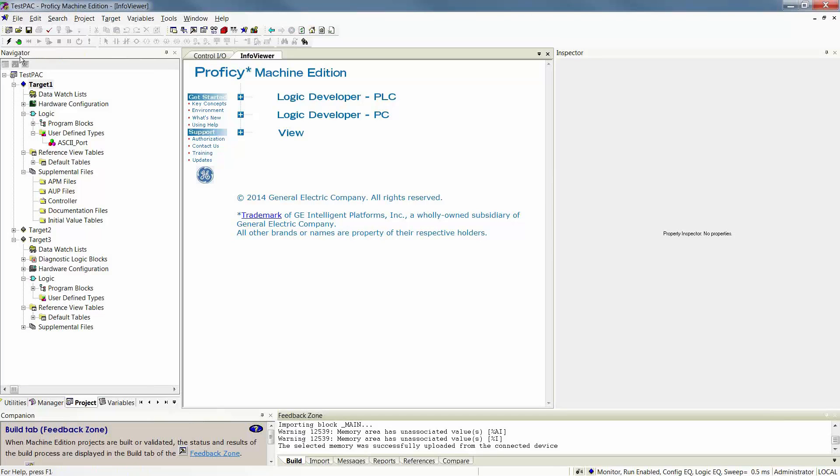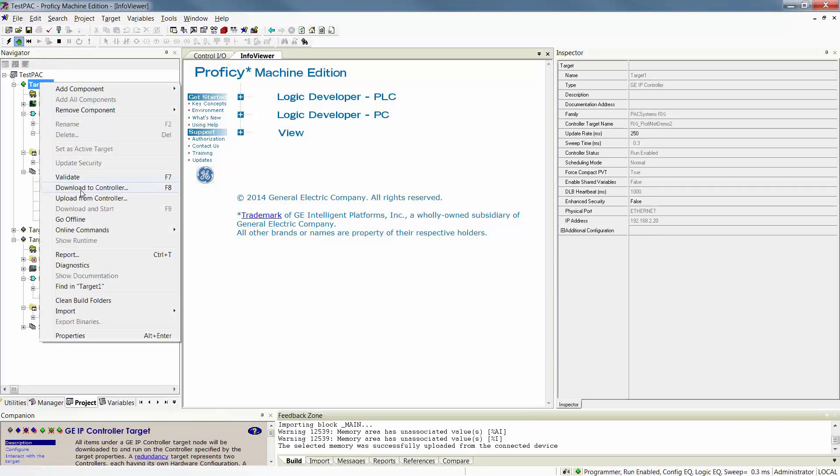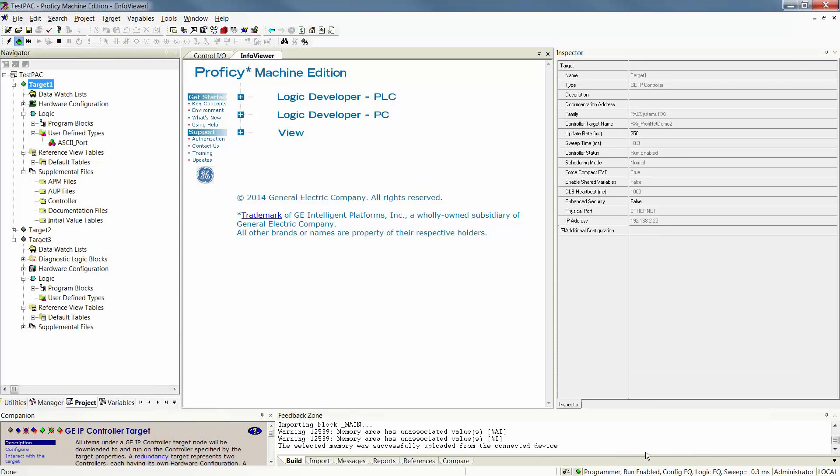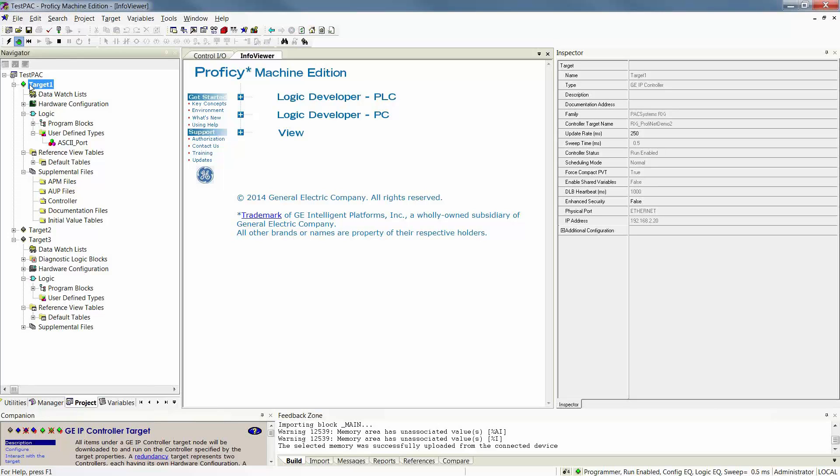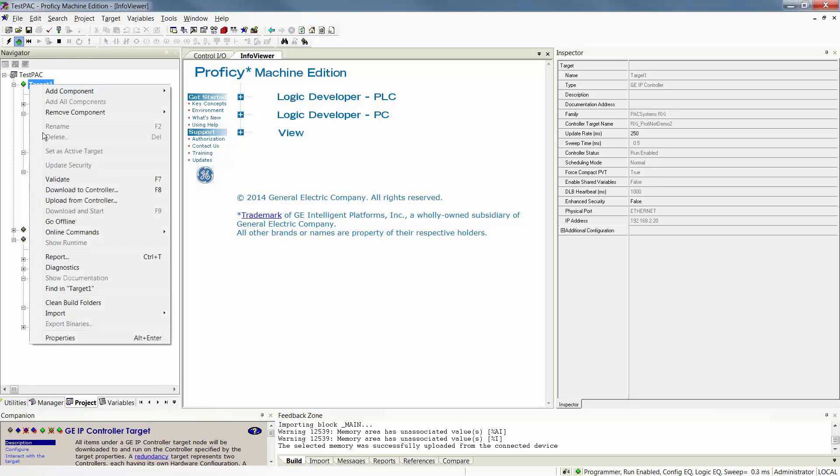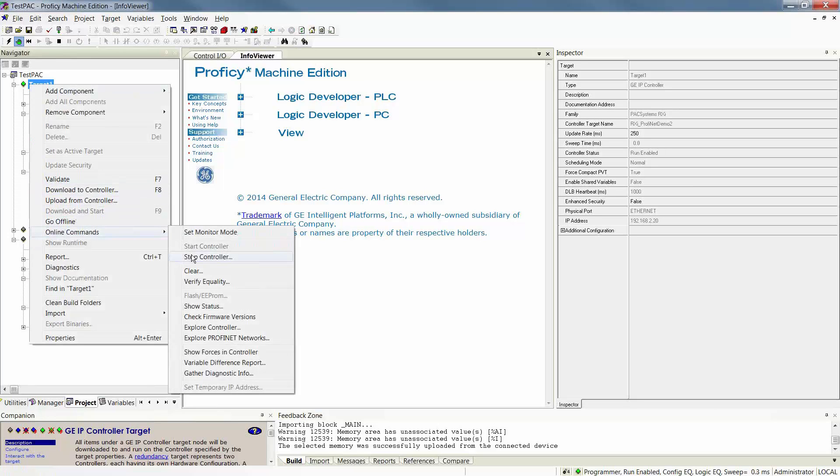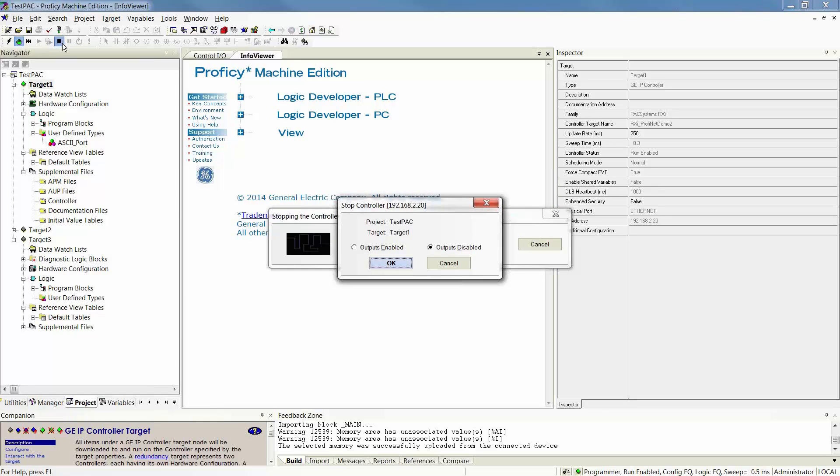You can also download, but you can only download if you are in the Programmer Mode. Now I'm in Programmer, so it will now allow me to download. Keep in mind that you can only download while running if it is a logic not equal situation. If your configuration is not equal, and that is what you're downloading to make equal, you will have to stop your controller. In order to stop your controller, you can either right-click on your target, go to Online Commands, and stop your controller, or use the shortcut stop button on your shortcut toolbar above.